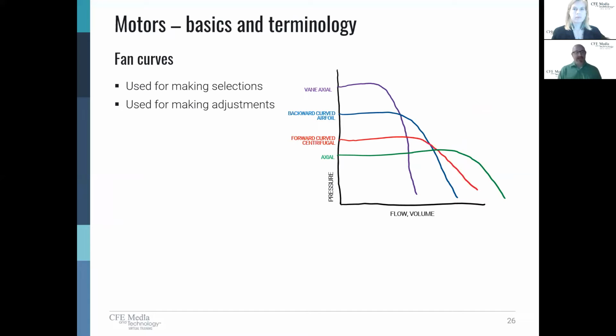It's important to understand that the fan energy index is a rating system to encourage better fan selections. So engineers need to be aware that the FEI, or fan energy index, is going to be useful to them to make the most efficient selection as possible. And it's based on the scheduled design or the scheduled duty point associated with that fan.